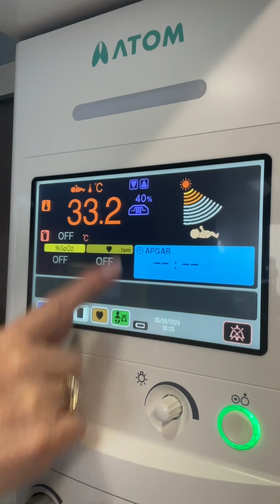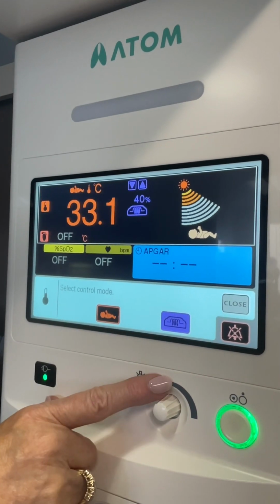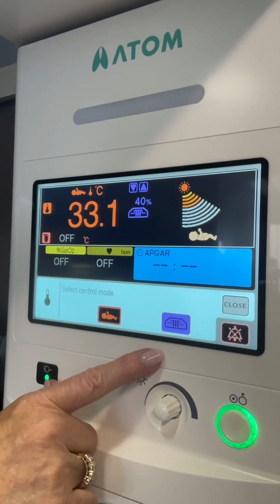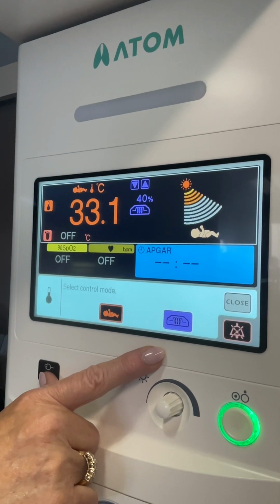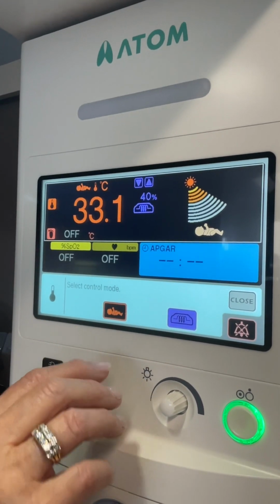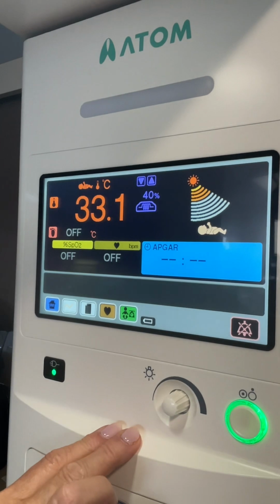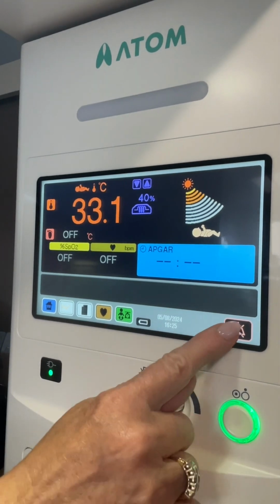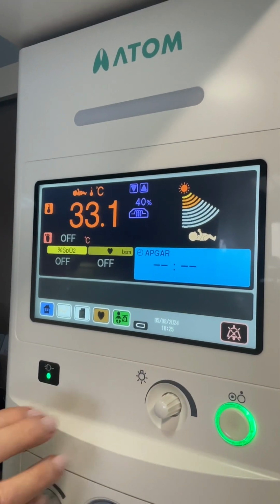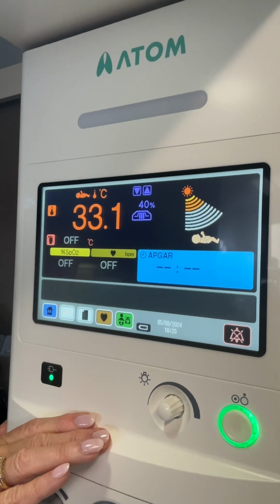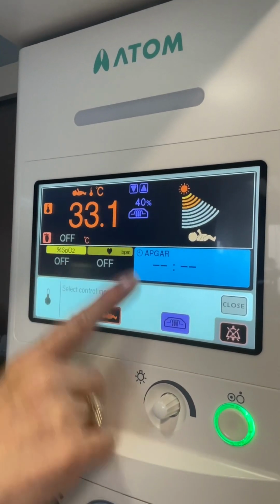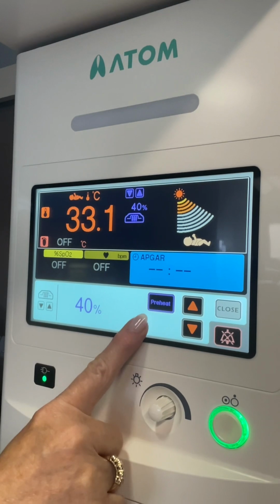Okay. By the way, in manual mode, any heat over that 35 or 30%, so 35 to 100, every 15 minutes, check baby alarm comes on. The heat will go to 0 because we don't want a baby overheating under heat they can't control. All you have to do is come check the baby, push alarm silence, and the heat will go back on for another 15 minutes.